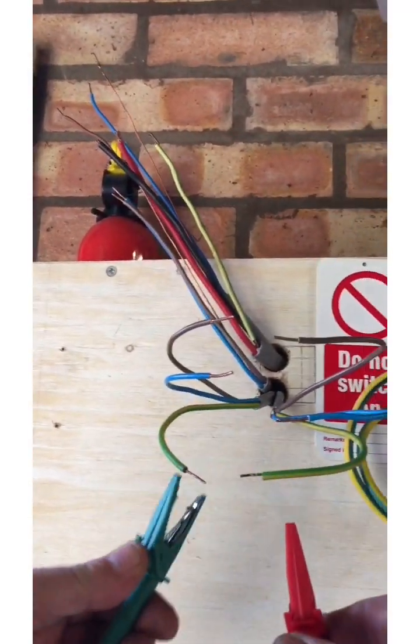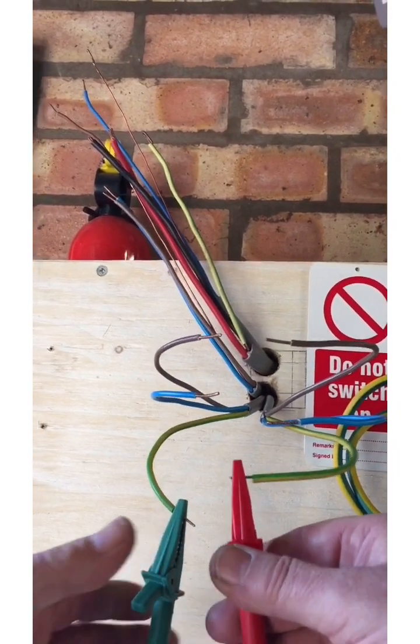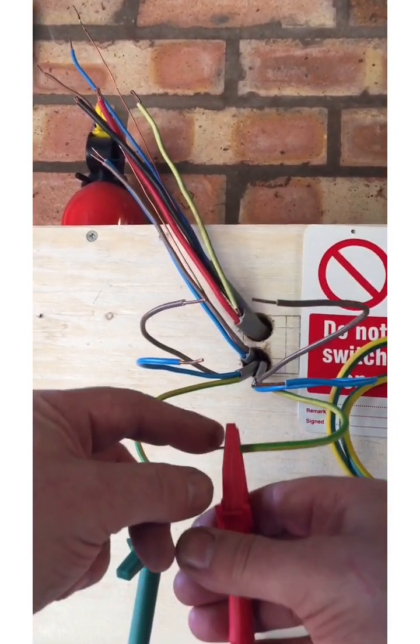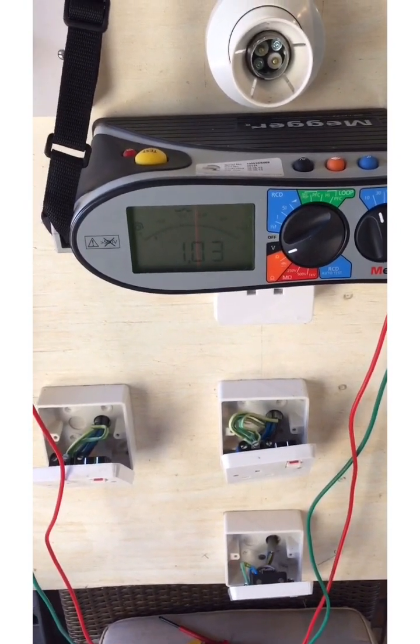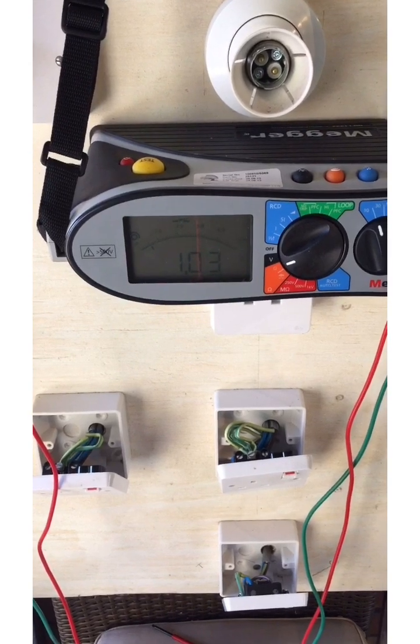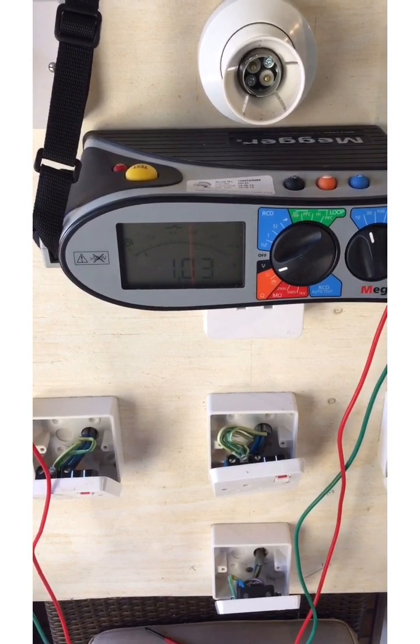And if we look at the CPC end-to-end on the CPC, and we're showing there slightly lower than I got before, 1.03, but we can work with that anyway.